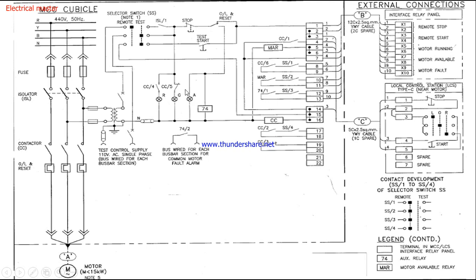Another indication is the amber lamp, used for tripping. As I told you, normally the phase supply connects to the NC contact of the overload relay. Whenever the overload relay detects any fault or overcurrent, it activates and opens the NC to switch to NO contact. So the NO closes and the positive supply connects to this lamp — indicating the motor has tripped due to overload. Similarly, relay 74 is connected here, used for external alarms. Whenever this relay contactor is activated, its NO closes and is used for local alarm and also to signal outside that the motor has tripped.